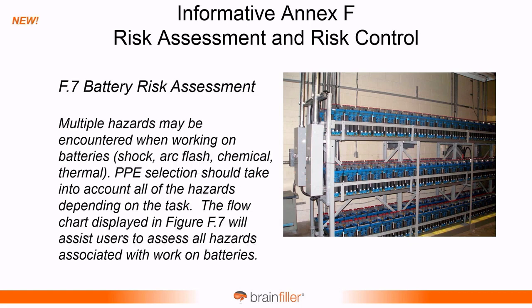F.7 is acknowledging that if you're working around battery systems, there's more than one hazard. There are multiple hazards, and they may be encountered when working on batteries. So you have the shock hazard, of course, possible arc flash hazard, but you also have the chemical hazard and the thermal hazard. And so it's acknowledging that the PPE selection needs to take into account all these hazards. And there's a flow chart to help with this.